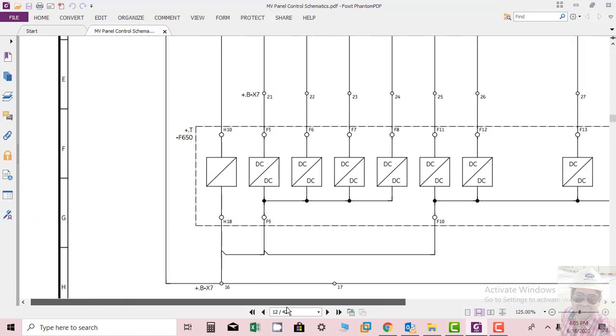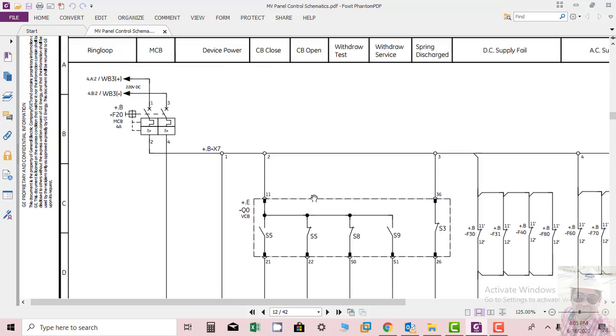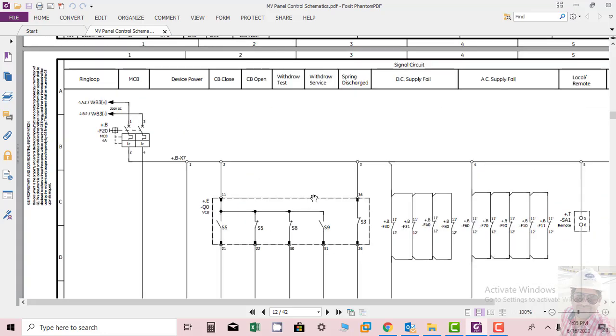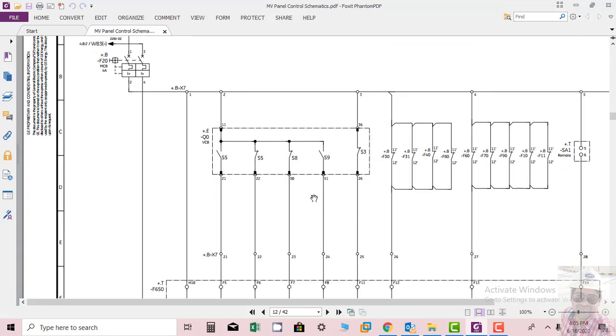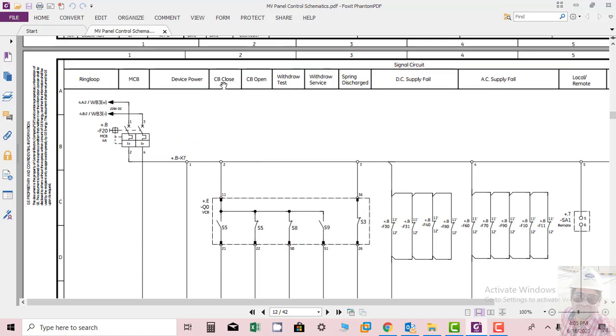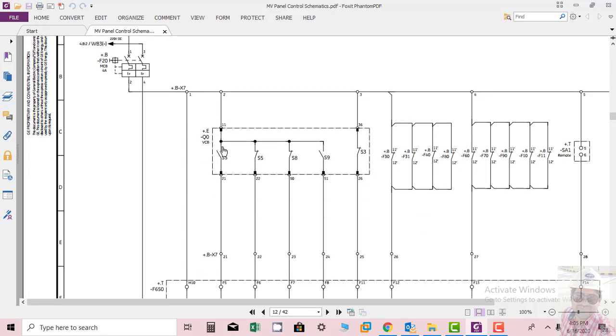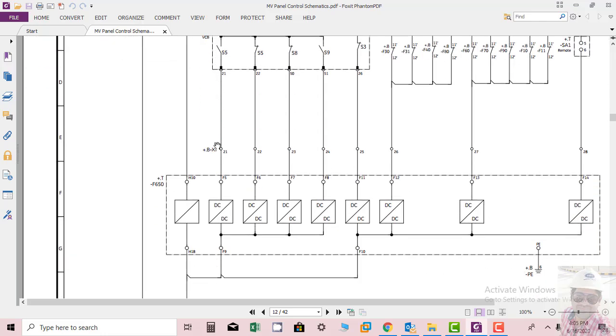Now let's see how many indications are connected to this relay. So this is basically circuit breaker close indication is connected. You can see this is Q0, and Q0 here is basically the circuit breaker open position. When the circuit breaker is open, it will be de-energized, and this contact is normally closed contact, so this will be energized, and this binary input 1 will be energized.